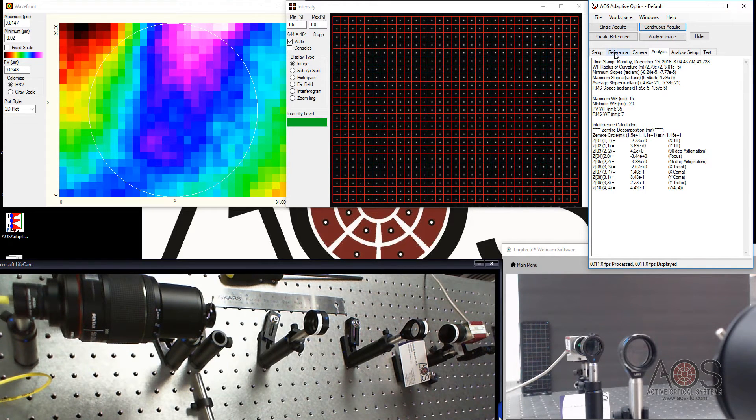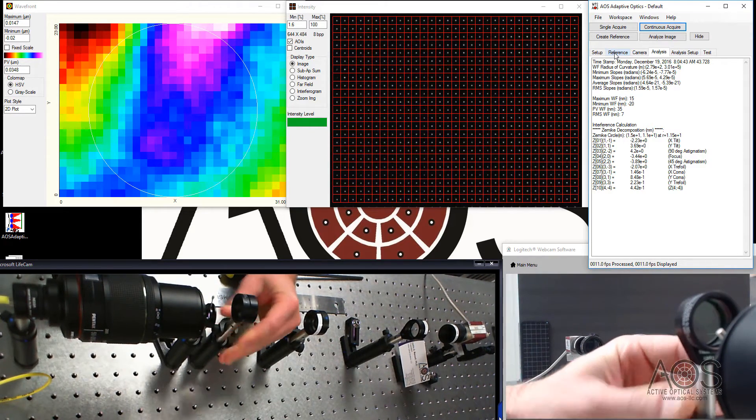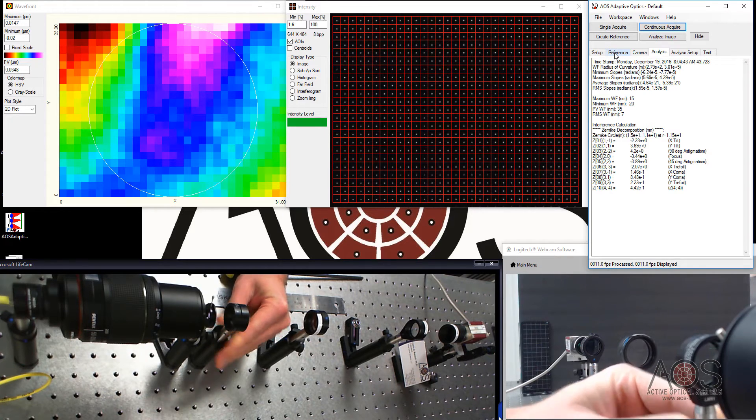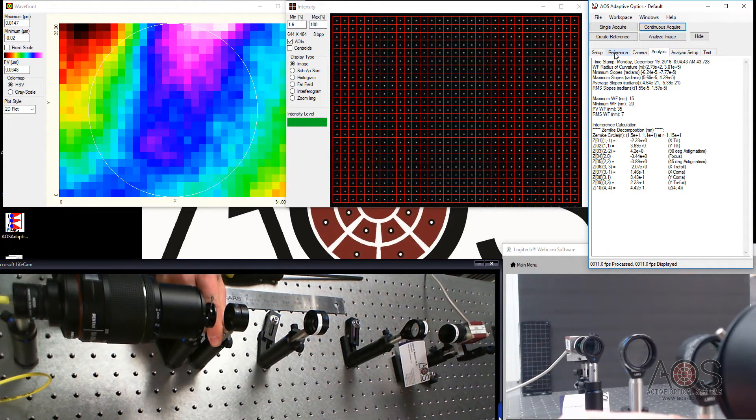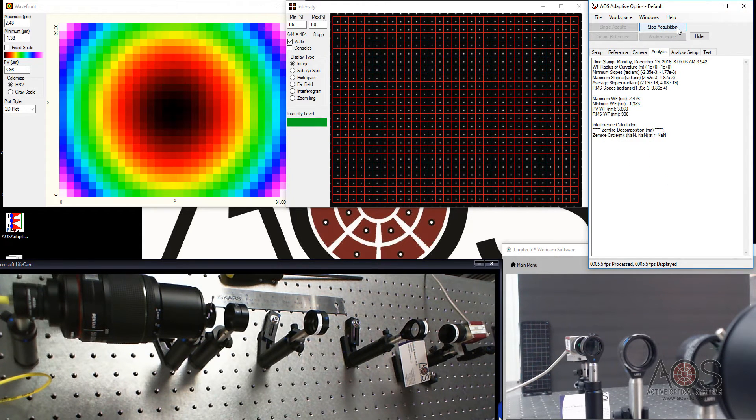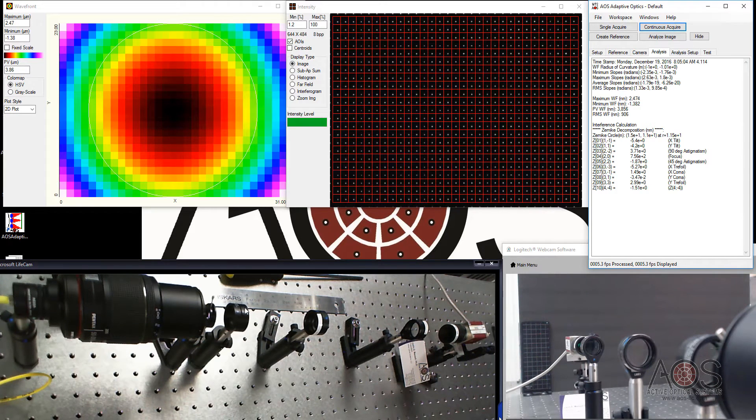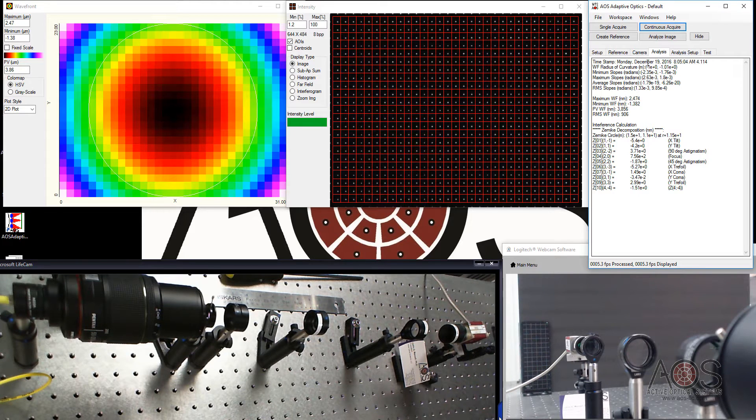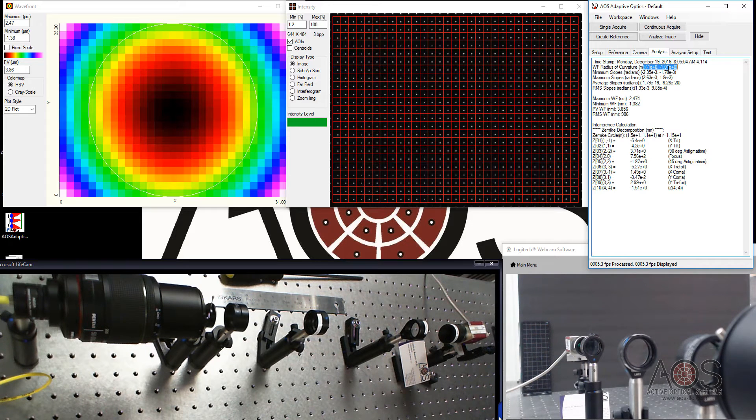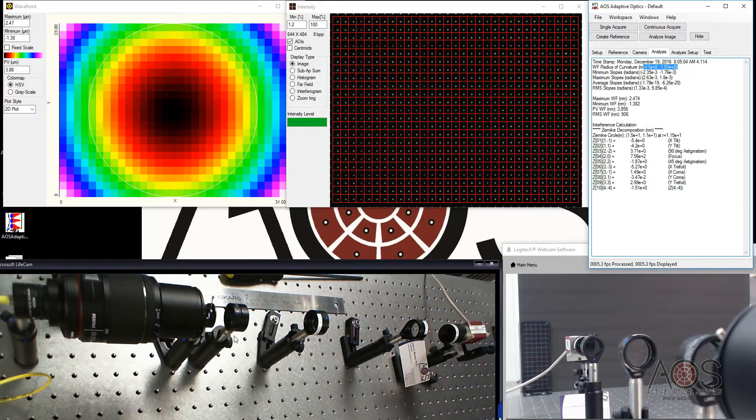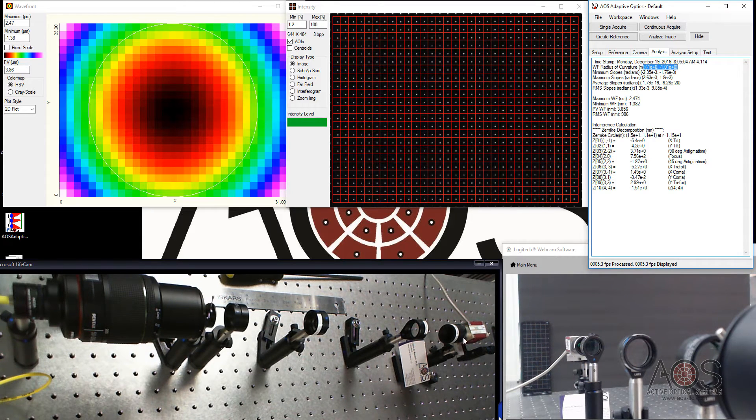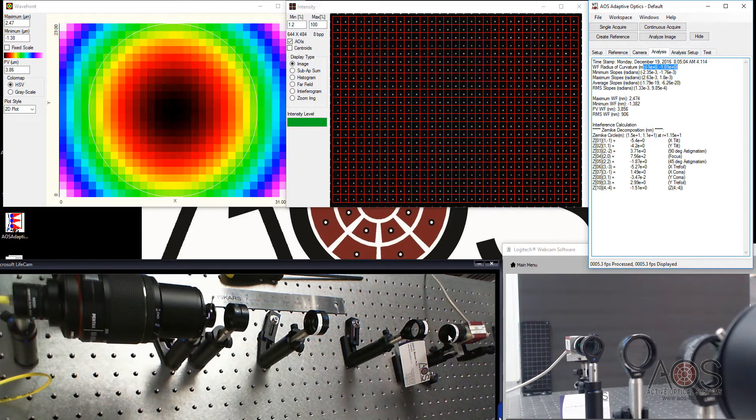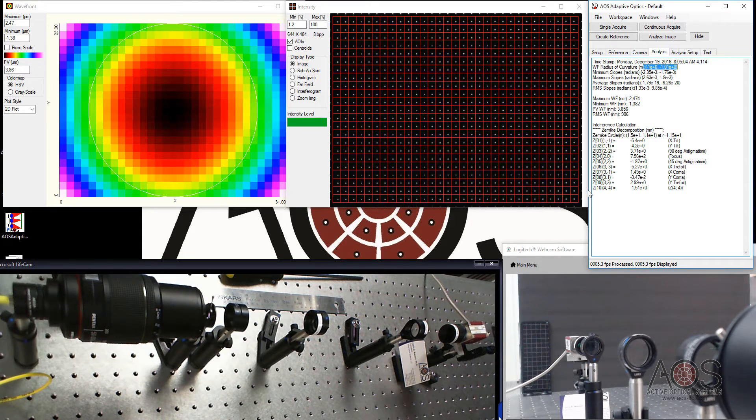Now I can drop in a device that I'd like to test. I'm going to drop in this 1 meter focal length lens. We're just going to take a look at it. I drop it in, line it up, and continuous acquire here. I've already set it up so that that lens is in the image plane of the lens array. As such, I am reading a radius of curvature of about 1 to 1.01 meters. This is the radius of curvature fit to the two axes. We're reading exactly what this device is designed to do. This is a nice way of re-imaging onto the lens array. And again, the reason for doing that, as I mentioned in the last video, is that when I put the lens directly in front of the wavefront sensor, there's a propagation distance between the lens and the lens array, and that affects the curvature that the lens array observes.